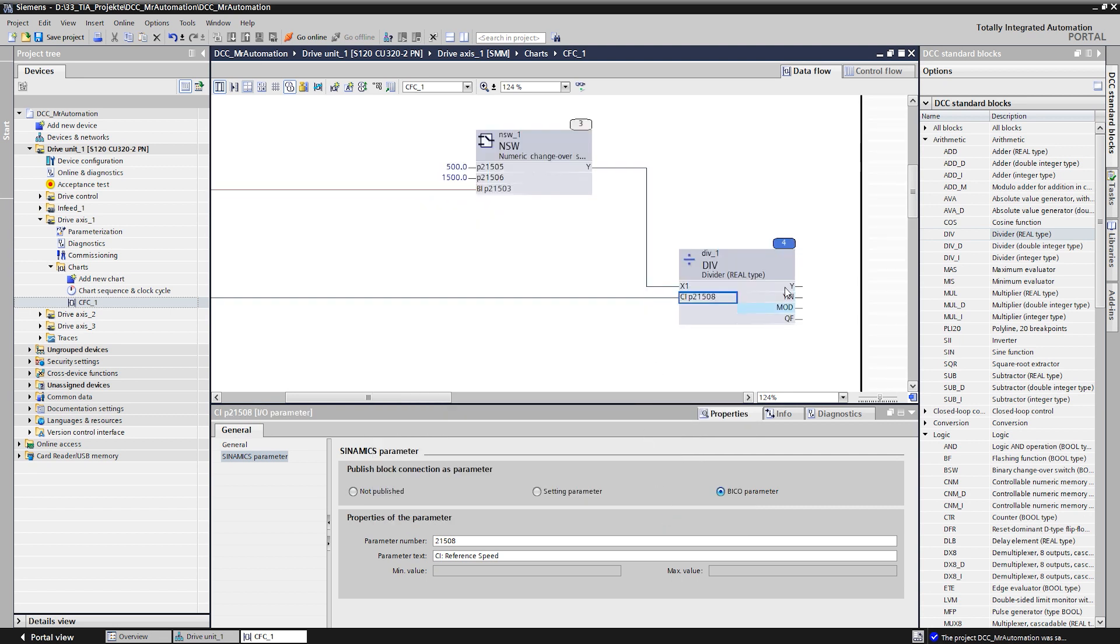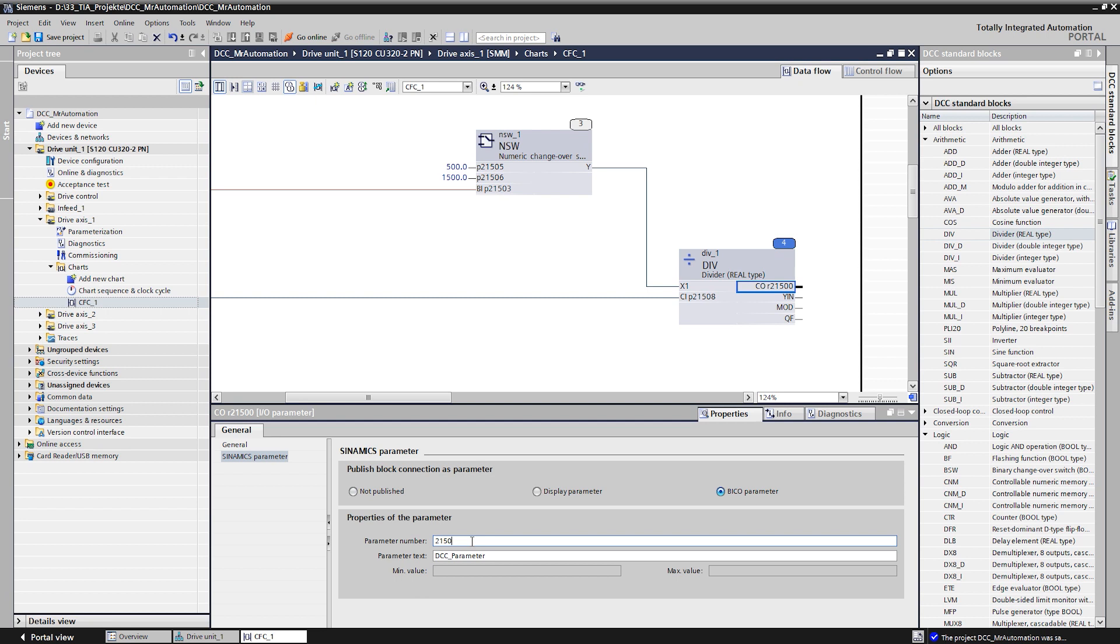The output is also published as BCO parameter to be able to connect it with a signal for the speed set point value in the basic system. We connect the calculated related speed reference value to parameter 1070.